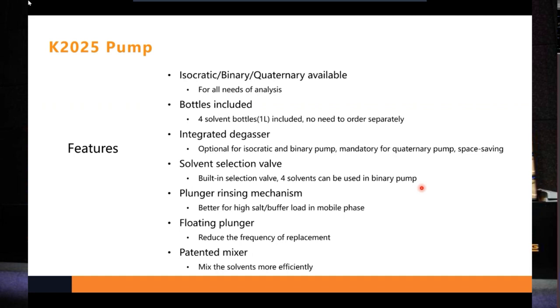The first unit should be the pump and the degasser, because the degasser is integrated into the pump, so I'll talk about them together. As I mentioned, we have isocratic, binary, and quaternary systems. All these three systems are available, and the bottles are included in the sales kit. We offer four 1-liter solvent bottles, and there's no need for the users to order them themselves. The degasser is integrated into the pump, but it is an optional choice for the isocratic and binary pumps, though we recommend equipping it with the pump. But for the quaternary pump, it is a mandatory part.